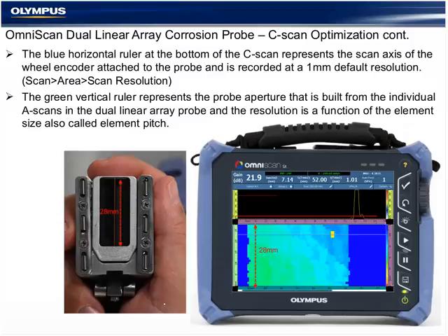So the probe face in a single line scan represents the A-scan first to A-scan last stacked vertically. This axis at 28 millimeters represents the entire length of the probe using the 5-element configuration. And the green vertical ruler for a 0-degree linear scan is volumetrically corrected, so it's millimeters to millimeters, whereas in an angle beam inspection, those of you that do OmniScan angle beam shear wave weld inspection would normally be seeing the C-scan in focal laws or apertures here. This is in real millimeters. That's possible only at 0 degrees.